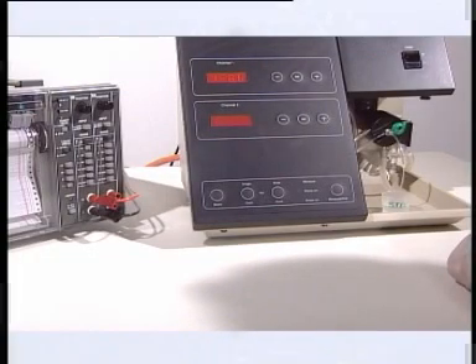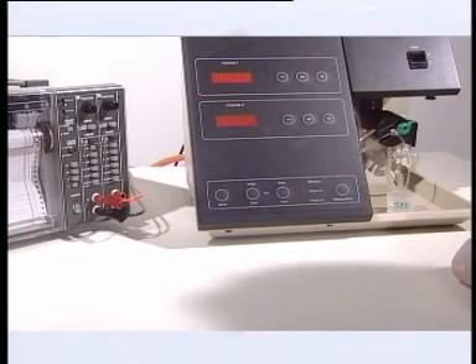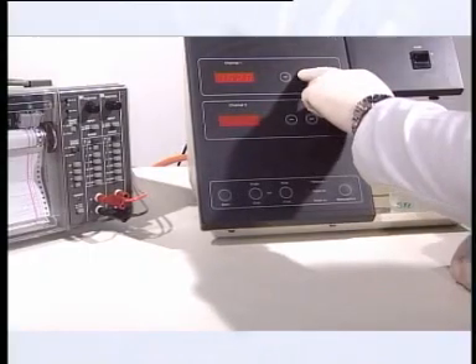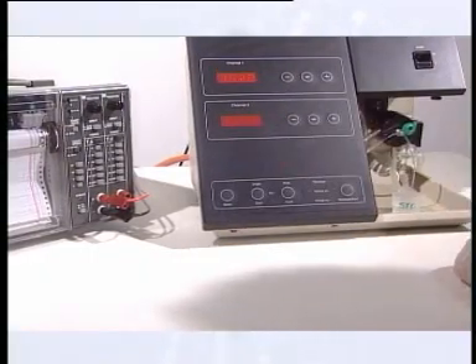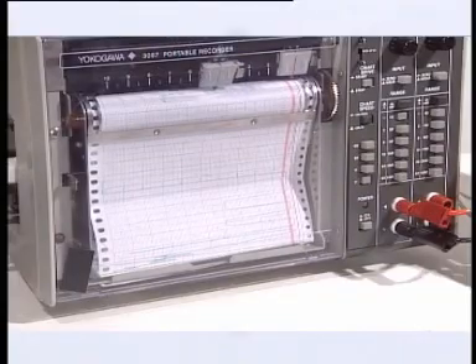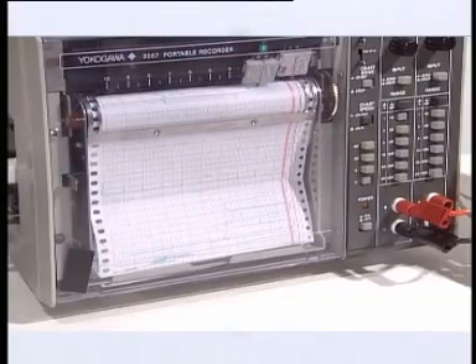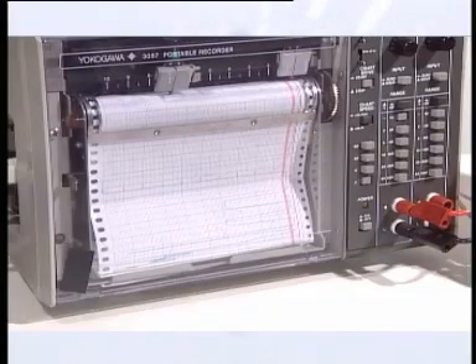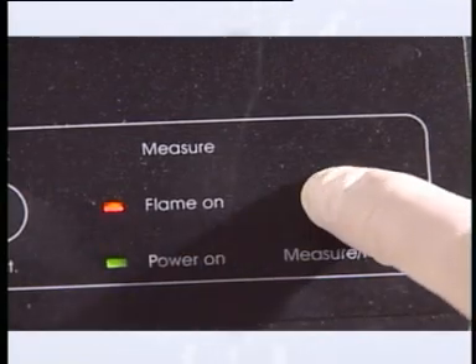However, when the calibration solution is aspirated, the user has to determine when the signal is steady. The set button is pushed and the measure light is illuminated. From now on, a continuous signal is fed to the analog outputs. It is possible also to get an instantaneous printout of the displayed values by pressing the measure button at any time.